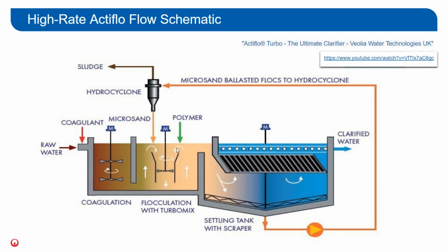It's getting a nice maturation, an easy mix through your mixer and draft tube to form those large popcorn flocs before they overflow to the underflow of the siphonal wall, at which point the clarified water will come in contact with the lamella pack before it overflows to the clear well as clarified water.